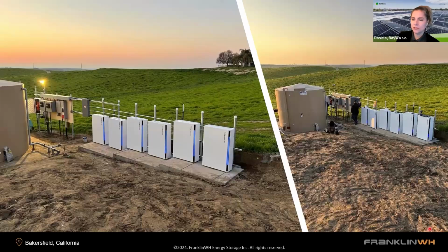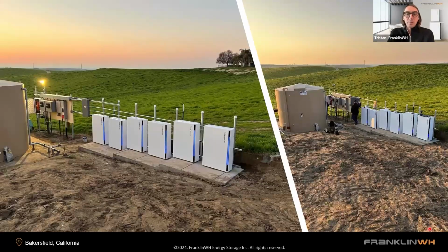All right. There's a couple more questions. Any static from inverter manufacturers about tricking them to stay on in grid-down scenarios, bypassing rapid shutdown? No, because the battery is completely grid forming, we don't have any issues with keeping the batteries online, and we use a relay. So it's a 0 or 1 type relay to turn them off. That allows us to be completely inverter agnostic, even for those very old legacy style inverters. We're not connected to any type of RSD device because we're connecting only to the AC output of a string inverter. So the RSD for the PV system is isolated. It's basically different than the Franklin system.